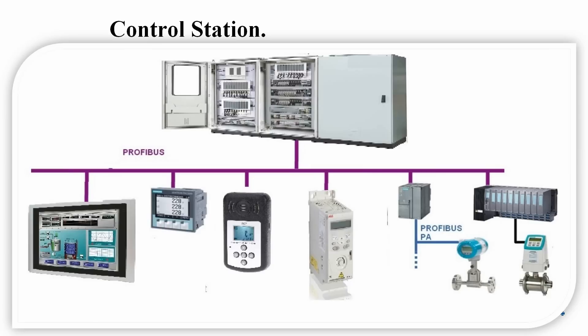Some signals go directly to the terminal blocks of the DCS. The story starts from sensing at the field level, where you have different devices all connected to the DCS. From the DCS, the next level is a switch connected via a fiber ring. The fiber ring is terminated at the switch, which is then connected to the LAN. On the LAN we have operator stations and engineering stations as well. That is the control station.